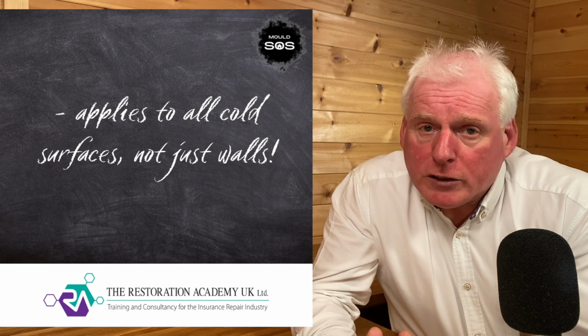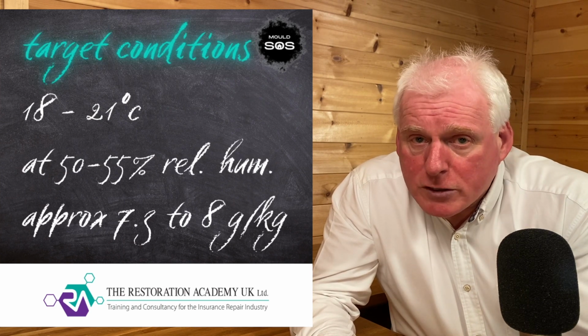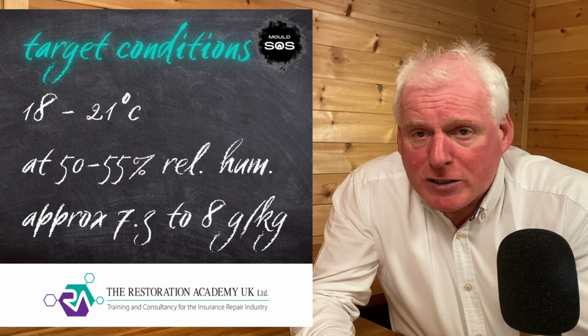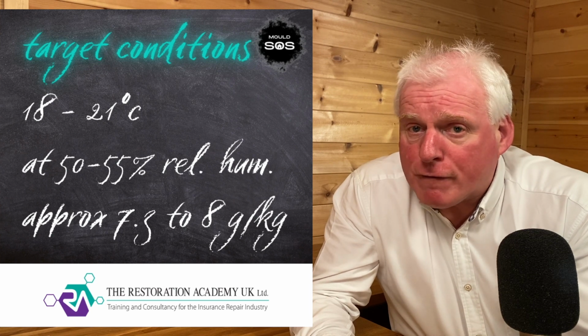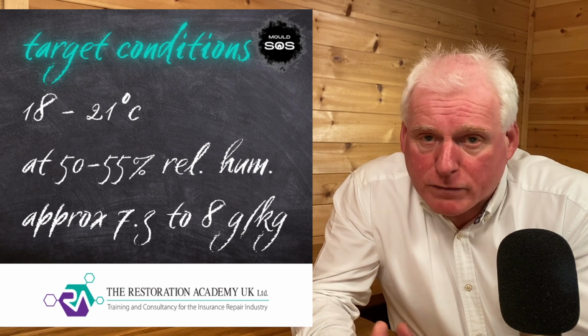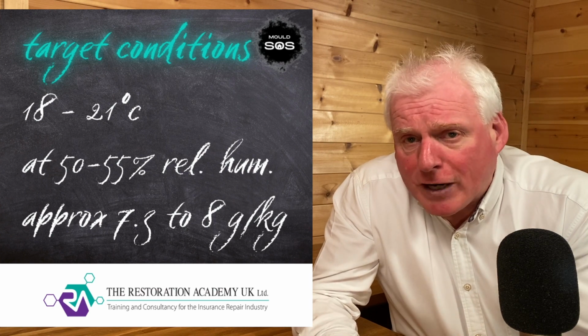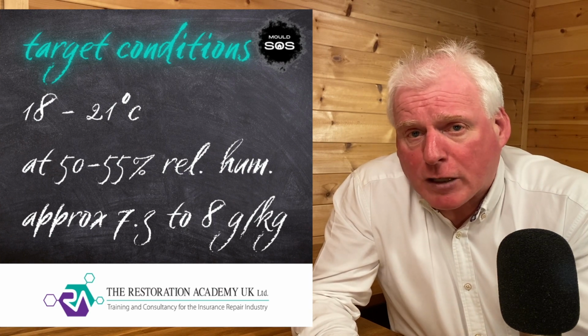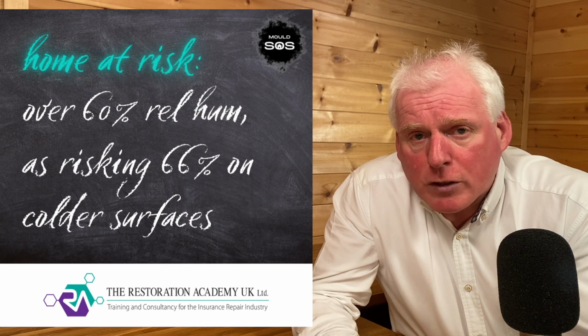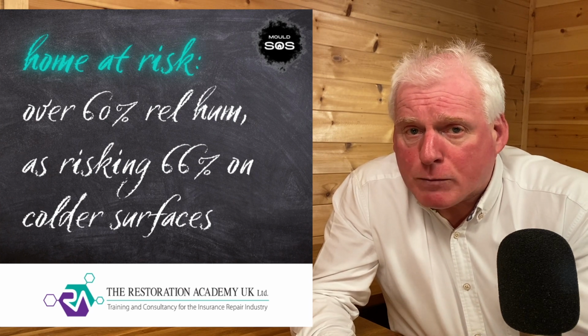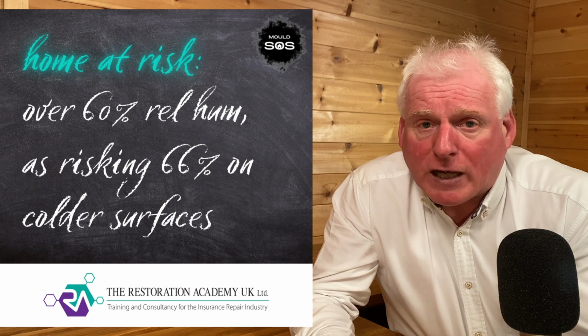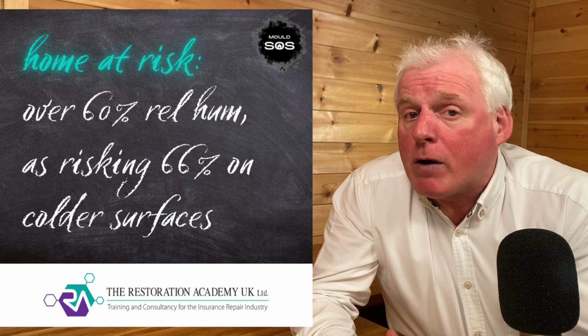So, what do we want our conditions to be at home? The short answer is to try to keep your home at 18 to 21 centigrade and an RH of between 50 and 55% for most of the time. This equates to a humidity ratio between 7.3 and 8 grams per kilogram. Your home is at risk when the relative humidity in your rooms is above 60%, especially when it translates to more than 66% on any mould edible surfaces where temperatures may be lower.